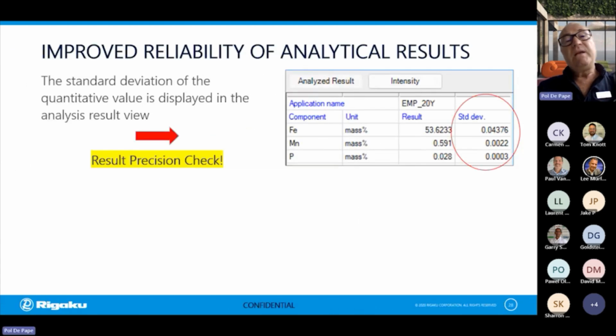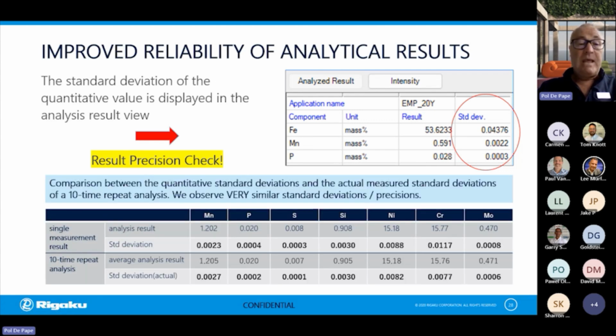We have also improved the reliability of the analytical results in the sense that for each measurement, we have now also introduced the standard deviation of this measurement, so you can really see the precision of the analysis. So if you have, like, iron 53.62%, we know that the precision of the analysis is like 0.043%. This is a big advantage because you have directly a precision check of your result. And this we can see in the table below.